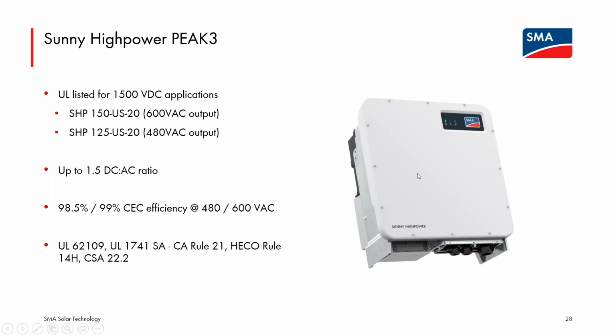There is not a combiner box as part of the PEAK3. SMA does not sell a UL listed combiner box for this inverter, but you will definitely need one for each and every PEAK3. My understanding for AFCI detection circuitry is there is a current limit for which they are functional, and the input current limit on the PEAK3 is way too high. So if the AFCI detection is needed, it would have to be occurring at the combiner box level. So again, some disqualifying factors for this not to be considered a rooftop device. So there may be other questions on that, but I just want to make that very clear.